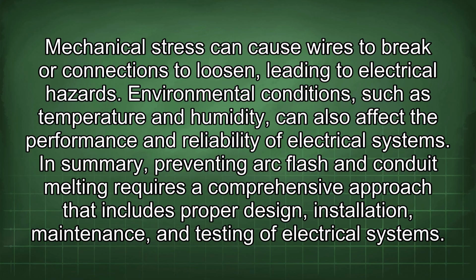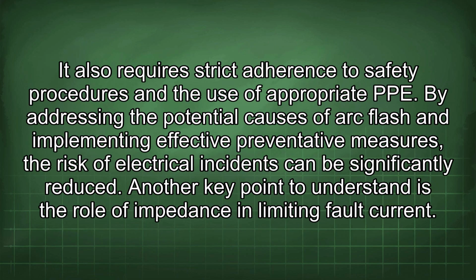In summary, preventing arc flash and conduit melting requires a comprehensive approach that includes proper design, installation, maintenance, and testing of electrical systems. It also requires strict adherence to safety procedures and the use of appropriate PPE. By addressing the potential causes of arc flash and implementing effective preventative measures, the risk of electrical incidents can be significantly reduced. Another key point to understand is the role of impedance in limiting fault current.